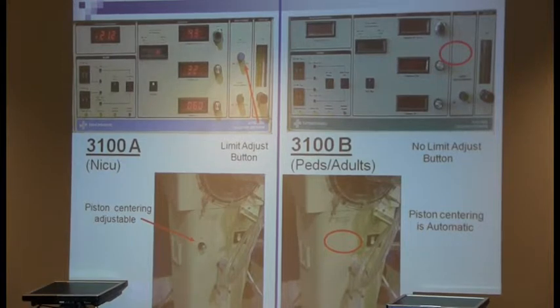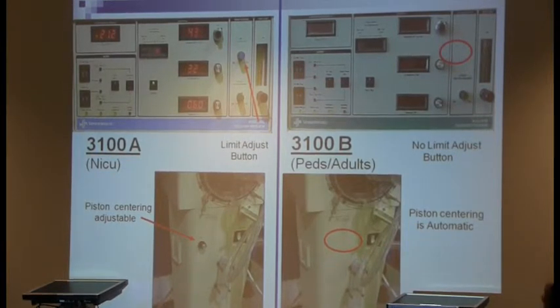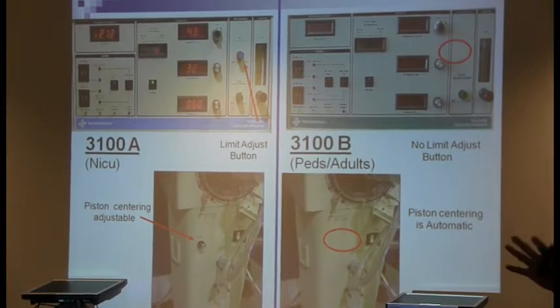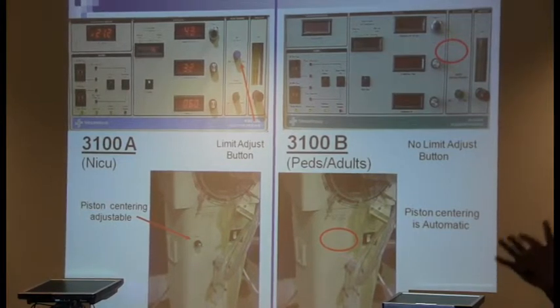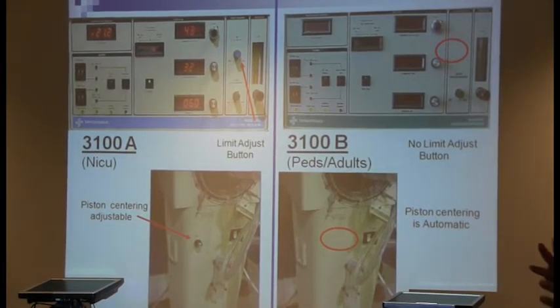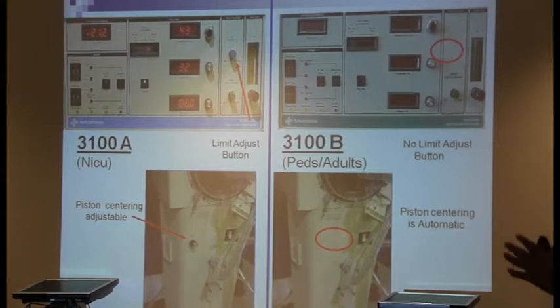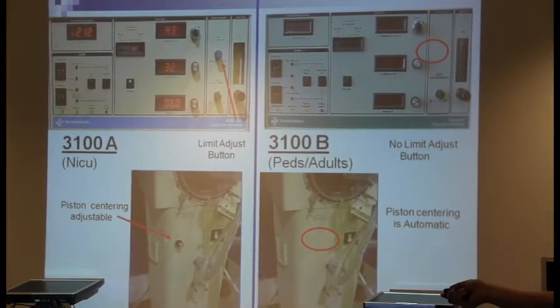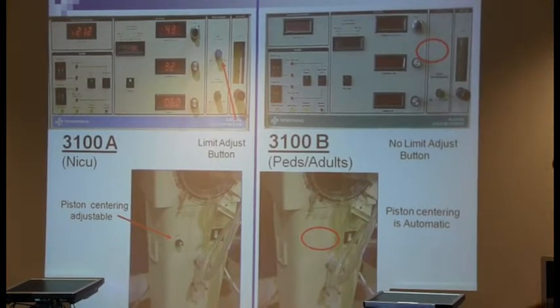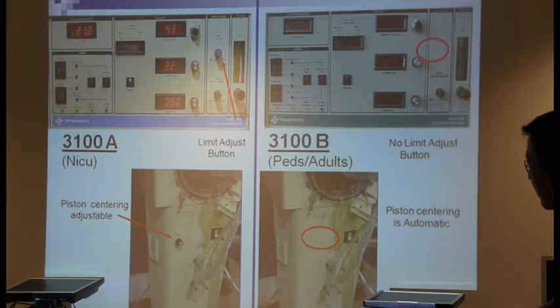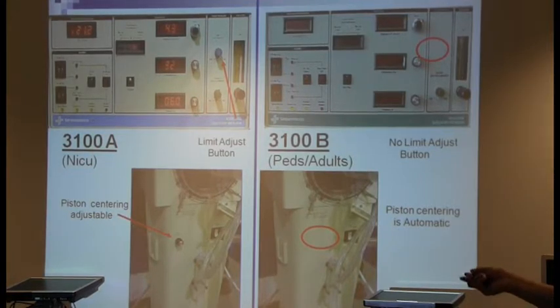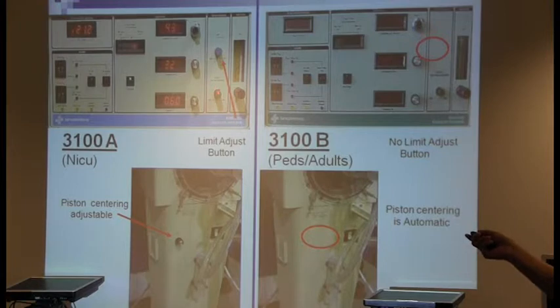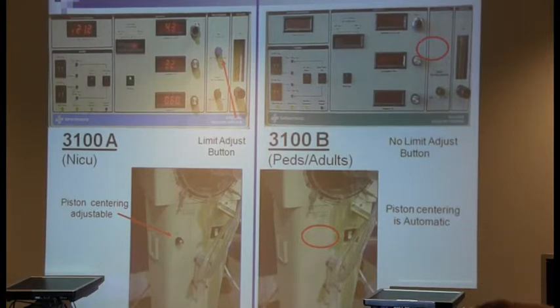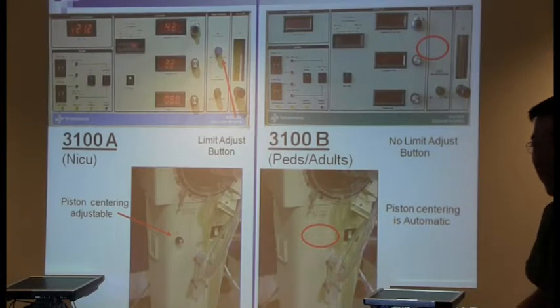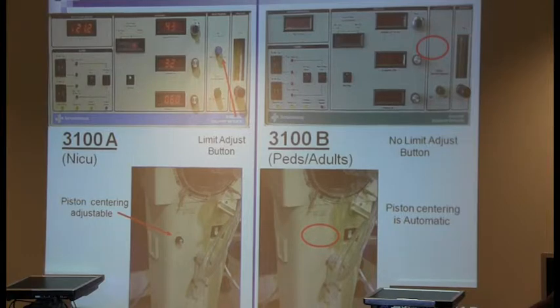Why is it that way? The B is a huge magnet, so it doesn't need to be centered. It's not that sensitive. But the A is a small magnet, so it always veers off. And so we want everything to be in line. So that's why we have to center it every single time, compared to auto centering here. Now, let's talk about the two buttons here. The green button says adjust. This is how you adjust your mean air pressure. This is the only way you adjust your mean air pressure.